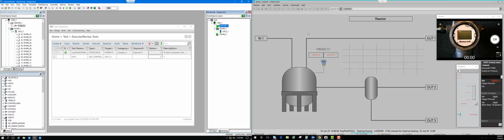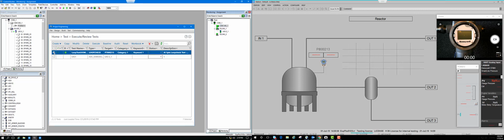Okay. Here to the right is an Experion Flex station that I'm using as my engineering commissioning station, as you will, or maintenance PC, where I have the PI800-213 pressure indicator. This is the instrument that I'm expecting to come in. I have a camera directly on the instrument so you can see the manipulation and the interrogation of the instrument from Experion. So in Experion, there is a service that runs. It's a HART service that initiates the loop test, the read and the write. So it writes 0 to 100%, and the instrument writes back to Experion saying, yes, I have achieved the 0 to 100%, which in my case is 0 to 20 pounds, 0 being my 4 and 20 being my 20 milliamps. Okay, so I think we should go ahead and just give this a shot.